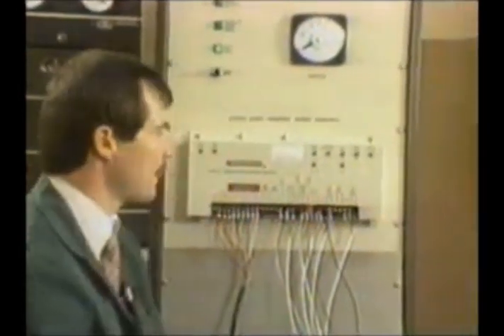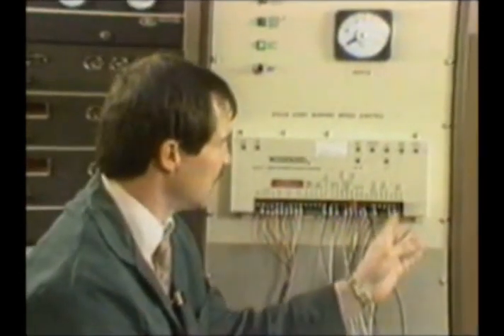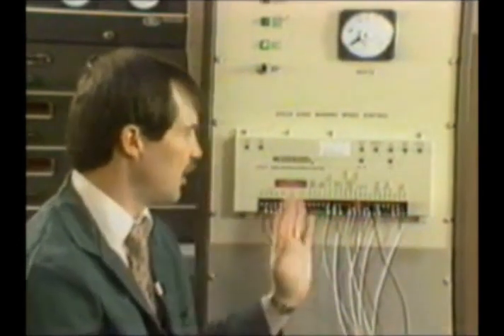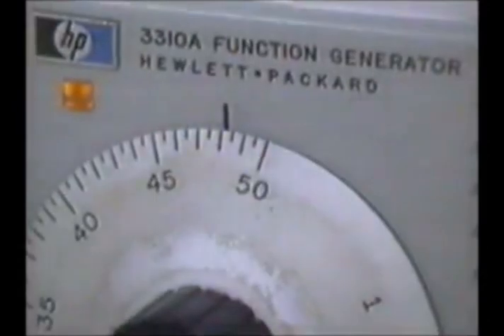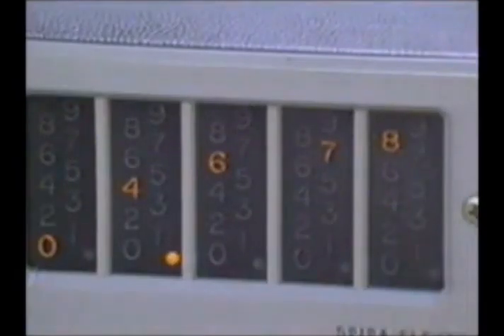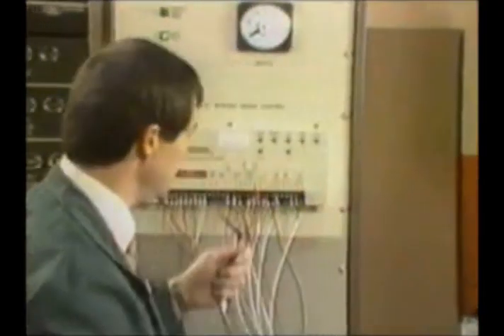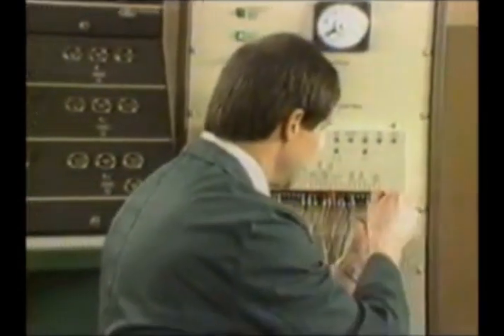Now what I want to do is I have a function generator available to set up my speed. So I'm going to use a function generator to go in instead of my mag pickup, to simulate a mag pickup. And by using my analog meter, I'll be able to find out where the 2301A wants to take control. Let me get over here. I have a function generator here set up, and you can see my electronic counter is reading 4678. And I want to go ahead and hook this on for my speed signal input. I need to unhook my speed signal input that's there, one side of it. So I'm going to unhook terminal 29. Now I'm going to hook up the function generator in its place.